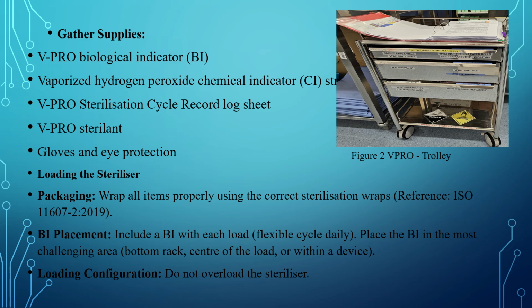Before we load the sterilizer, make sure your RMDs are packed into the proper packaging using correct sterilization wraps, and also the IFU has been followed, like for example a cycle running with the flexible cycles. The placement of the BI is supposed to be on the bottom rack or center of the load or within the device. Load configuration: do not overload the machine.